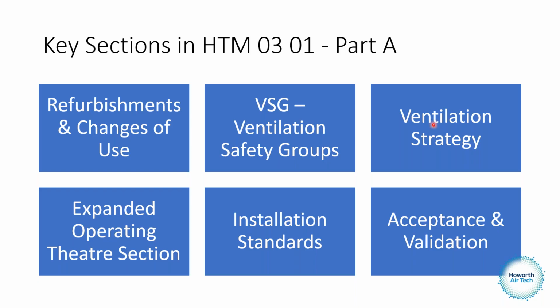There's an expanded operating theatre section, and then there's installation standards, such as making sure that I can get to the VCD handle within the space. You'd be surprised how many hospitals were manufactured with a VCD against the wall, behind a light, that once it was all in, you couldn't get to. And also we have ductwork pressure testing, in situ air handling unit testing, and lots of other different things, permeability testing of the room, all that should be done. And then finally, acceptance and validation.